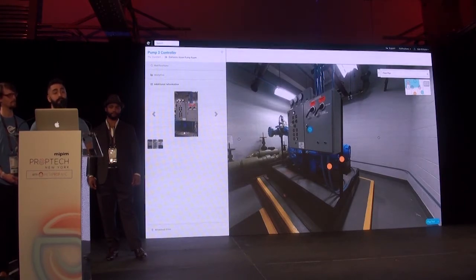And from an installation perspective, it's standard electrical subcontractors for the most part when it comes to sensor and device deployments, in and out of a building in 1 to 4 days, depending on conditions. No permitting requirements, no power shutdown requirements. And then there's the commissioning of data, which comes from putting in cellular gateways to get the data out, not having to deal with internal IT or cybersecurity concerns. And then it's doing data quality checks in our back end for the first few weeks.